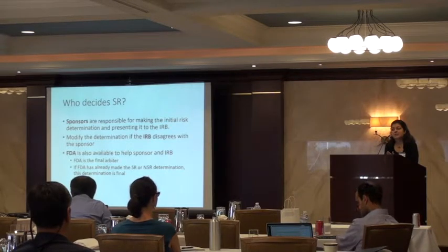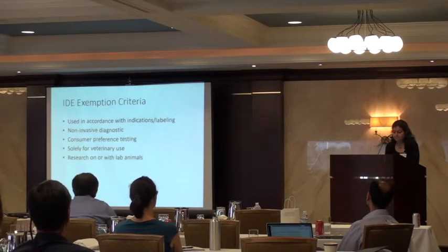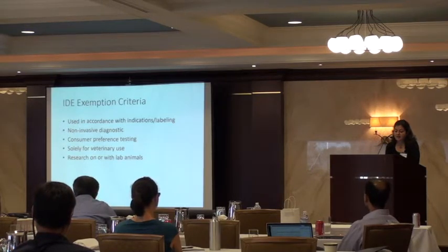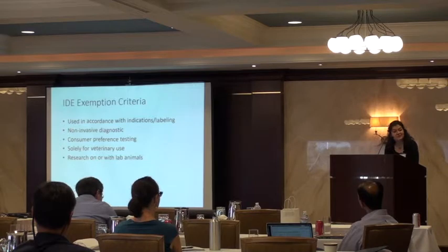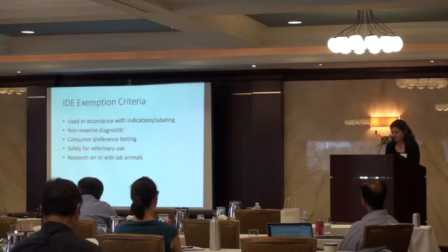And at this point, let's say you're doing an NIH application for a clinical trial, you actually have to have already applied for your IND or IDE at the time of submission. So it's good to get that ball rolling. IDE exemption criteria are basically those that are in accordance with the indication and labeling, non-invasive diagnostics, although it sounds like you just gave me an example, Rob, of a non-invasive diagnostic that did need an IDE, consumer preference testing, veterinary use, or lab animal research.